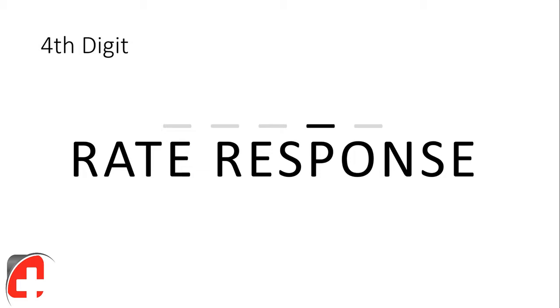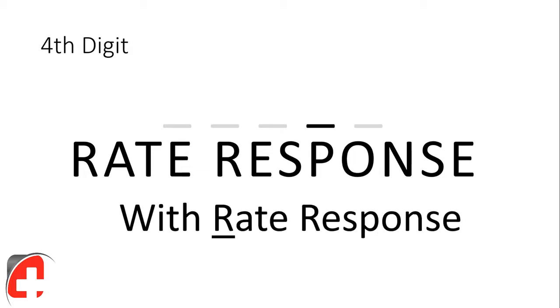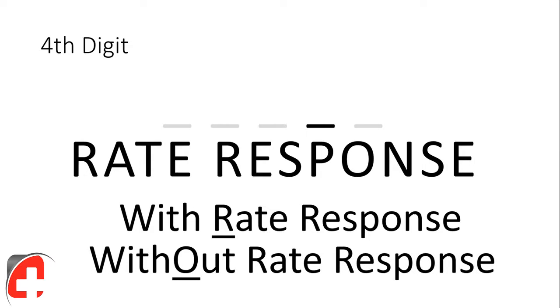So the next thing we need to talk about is the fourth digit. Now, the fourth digit used to have a slightly different purpose. The fourth digit used to denote programming options, like whether you could communicate with it with set parameters, like sensing, output, more complex features like event recording, and whether it's able to accept parameters. And pretty much all pacemakers nowadays, since the 1970s, have had some degree of programming. Almost all of them now are multi-mode programmable, so they have a full feature set of things that can be programmed and tailored to the individual patients. So that's more or less gone out the window. All that it's being used for now, the only other thing that it could tell you, is whether it is rate responsive or whether it is without rate response.